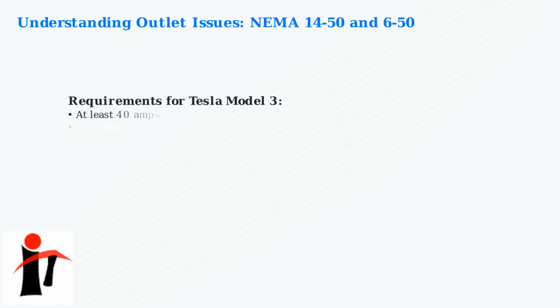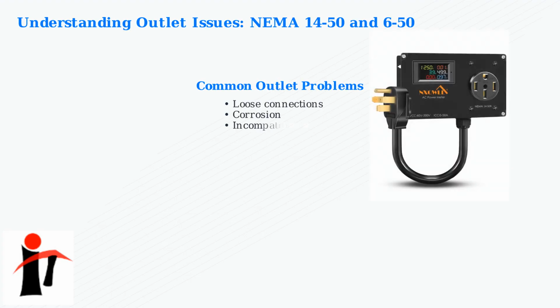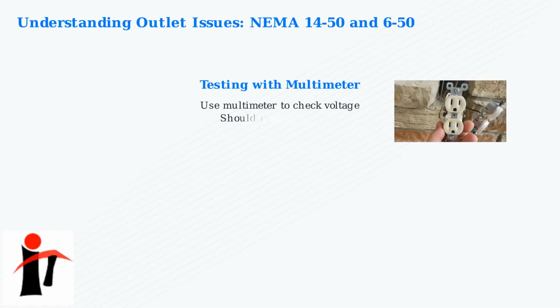Both outlet types must be rated for at least 40 amps and 240 volts to safely charge your Model 3. The wiring must also be compatible with these specifications. Common problems include loose connections that break the electrical path, corrosion that increases resistance, and incompatible wiring that can't handle the current. To diagnose outlet issues, use a multimeter to test the voltage. The reading should be between 220 and 240 volts for proper operation.